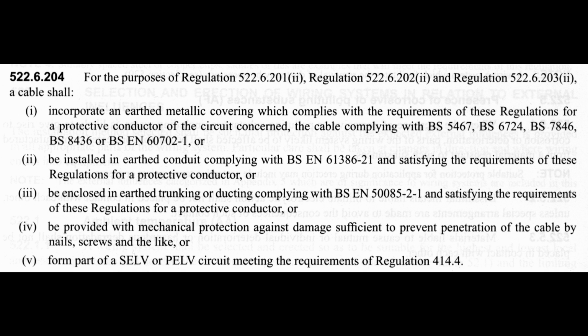So essentially, if you're going to put cables in the wall outside of the zones, they've basically got to be in steel conduit or steel trunking or something similar, or they've got to be an armoured cable such as steel wire armoured or the sort of copper clad varieties or various other types. So generally a fairly uncommon choice, but bearing in mind that these do exist, and if you do need to put cables in places where the zones are not actually applying, then there are these options.